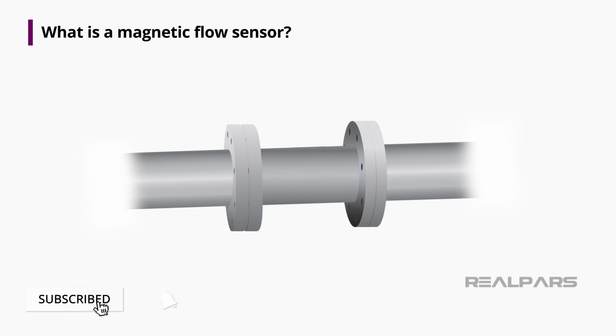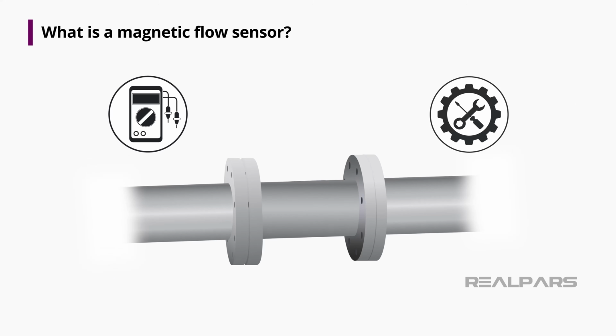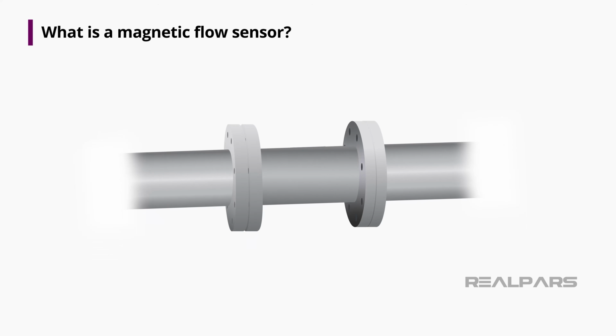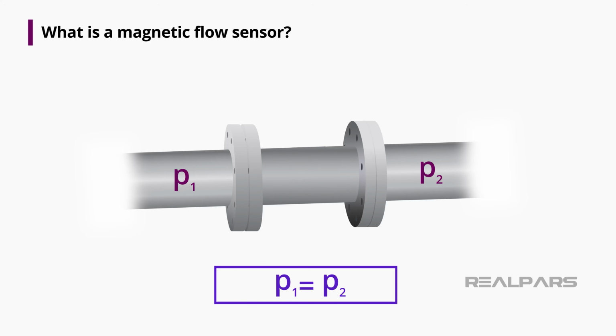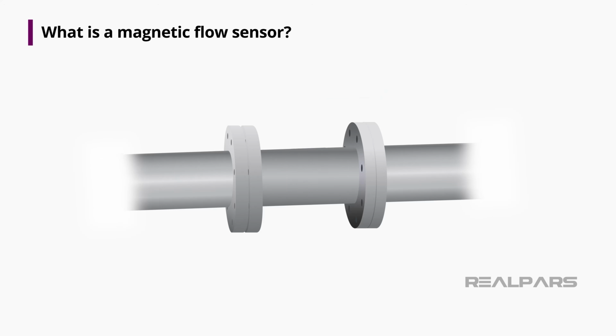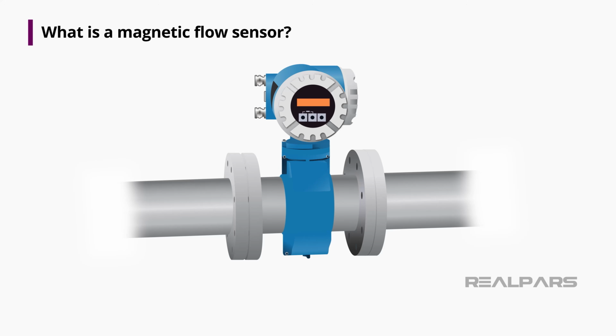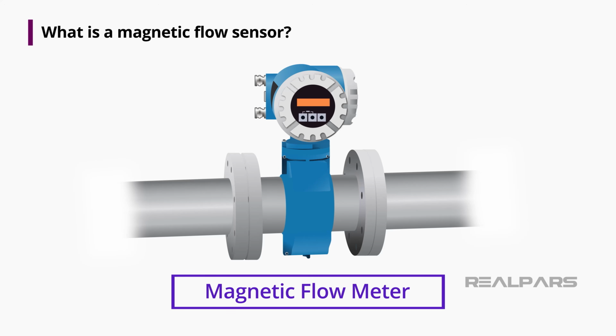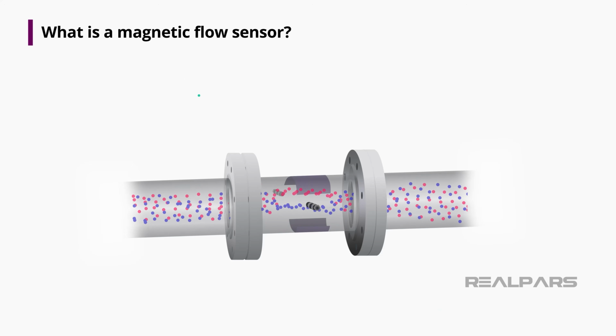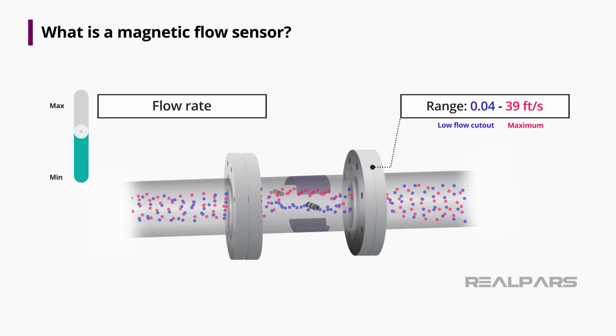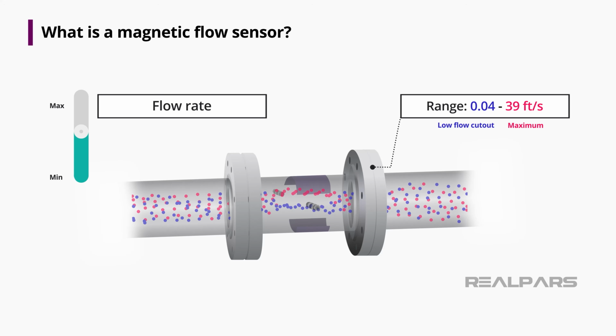Magnetic flow meters have no moving parts or internal flow path obstructions, so they are easy to calibrate and maintain. Because magnetic flow meters are typically specified to be the same size as the upstream and downstream piping, there is virtually no pressure loss through the flow meter, which can be very advantageous for some flow streams, like thick slurries. So let's take a look at these properties and characteristics of magnetic flow meters. I will explain how they work, when to use them, and what needs to be specified to select the proper sensor for your application.